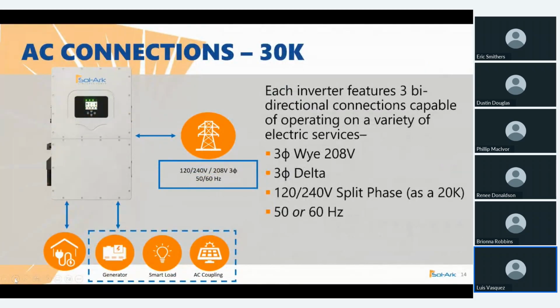Then we have the AC connections. The Sol-Ark can be connected to a generator, which of course has to be 3-phase, and we can use the same connection for smart load. Smart load is a function of the Sol-Ark that lets us use the gen input as a load output. This is useful when we have a full battery and the loads aren't demanding much power, but we have a lot of PV power available - we can send that power out through the grid breaker and the gen breaker to get a bit more capacity on the battery and use all that available PV power.